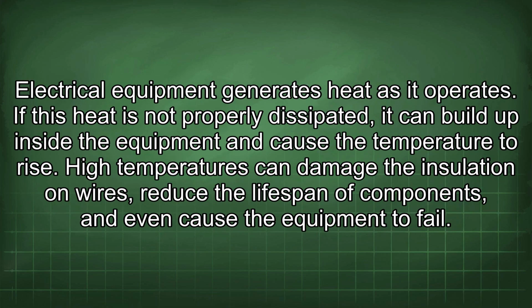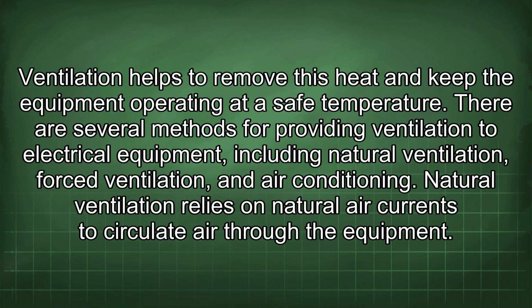Electrical equipment generates heat as it operates. If this heat is not properly dissipated, it can build up inside the equipment and cause the temperature to rise. High temperatures can damage the insulation on wires, reduce the lifespan of components, and even cause the equipment to fail. Ventilation helps to remove this heat and keep the equipment operating at a safe temperature. There are several methods for providing ventilation to electrical equipment, including natural ventilation, forced ventilation, and air conditioning.